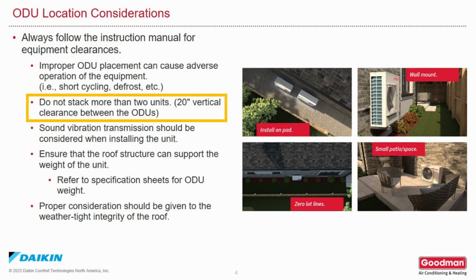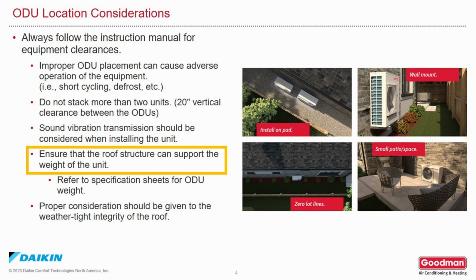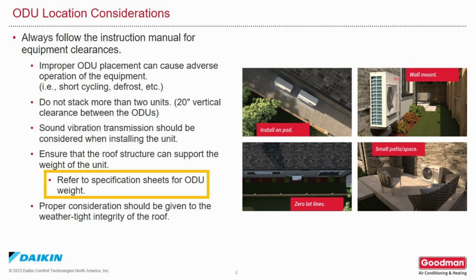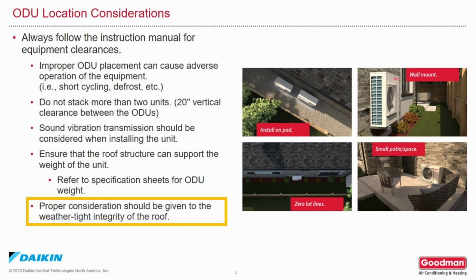If you're going to stack units vertically on the wall, make sure you limit it to no more than 2 units with a minimum of 20 inches of vertical clearance between them. When mounting an outdoor unit on the wall, roof, or deck, please consider vibration transmission, which could cause noise. If mounting a unit on the wall or the roof, make sure the structure can support the weight of the unit, and you follow proper steps to keep a weather-tight integrity of the roof or wall.